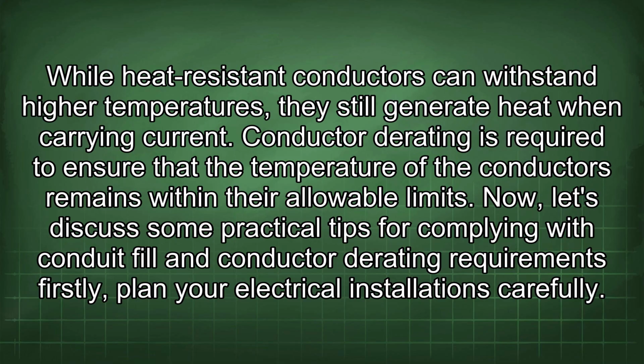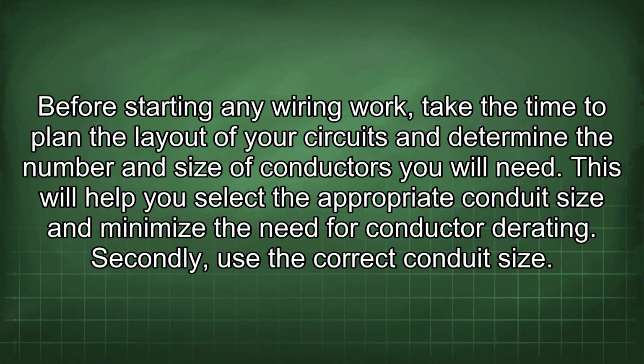Now, let's discuss some practical tips for complying with conduit fill and conductor derating requirements. Firstly, plan your electrical installations carefully. Before starting any wiring work, take the time to plan the layout of your circuits and determine the number and size of conductors you will need. This will help you select the appropriate conduit size and minimize the need for conductor derating.